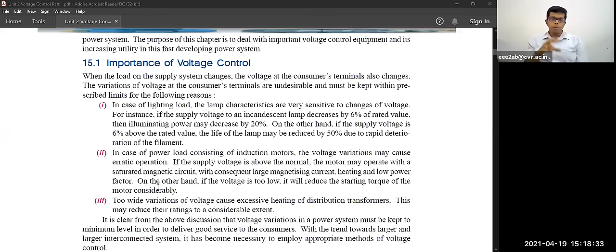Also, if you are running with a low voltage, the speed of the motor will be very less. Then the pumping power you are using for pumping water will decrease. Sometimes only the motor will rotate and it will not pump the water. I'm not talking about the underground submersible motor, but the motor you have above the ground tank. With that motor you can really hear the sound changing. If you go near and touch that motor, the heating will sometimes be heavy. Sometimes only sound will be coming and the motor will not be pumping. Many issues are happening.